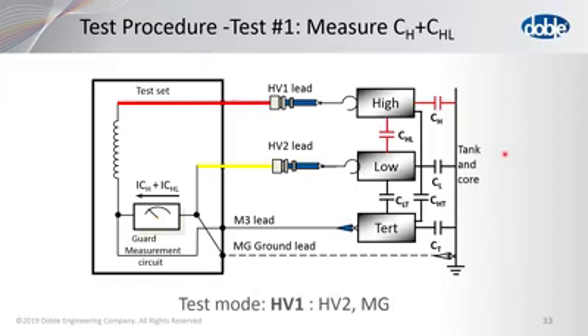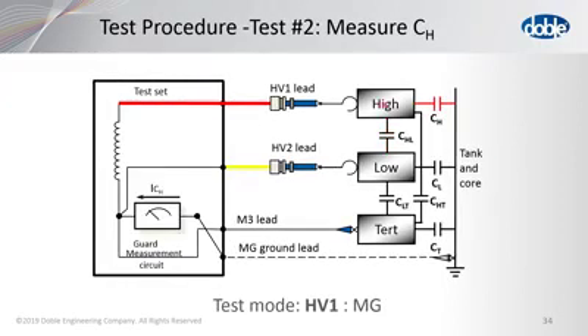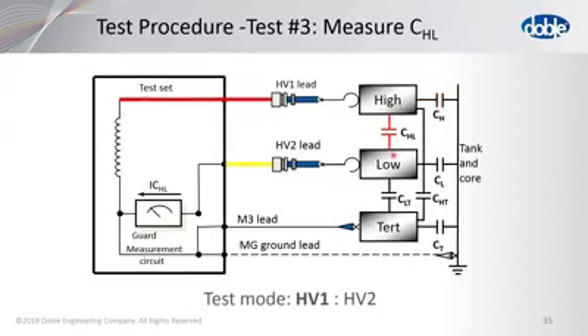I'm going to go through 2 more slides. Notice again, we're still energizing HV1 for test number 2. We follow down through this circuit, and notice we measure. Notice that anything going this way is guarded, is not measured. See how it did not go through the measuring network? And then I'm going to show this one also. Notice it does not go through the measuring network. And lastly, when I energize this and go down through this capacitor, notice I measure that one. Any current going to ground is not measured. See how the current through that circuit does not go through the measuring network? And lastly, if you follow down through this insulation, notice that is also guarded. Hopefully that answers your question.